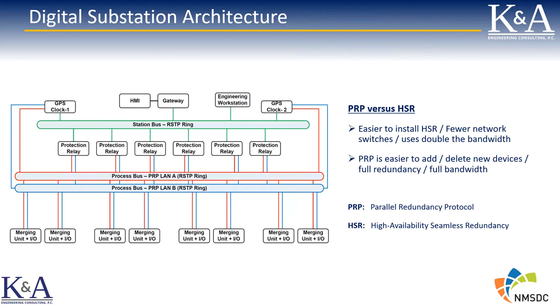And actually in the IEC 61850 projects that I have done, we've also made the station bus redundant as well, not just the process bus, but the station bus as well. Next, please.